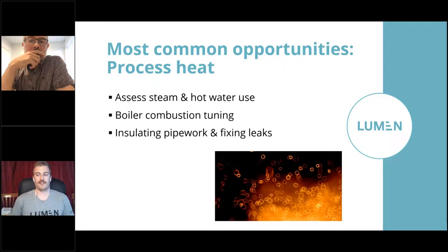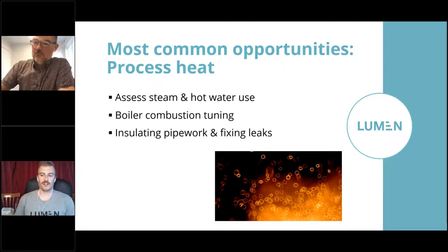The first thing we always recommend is to assess the steam and hot water use. Where's it going? How much is being used? Do we actually need that much? A good example is meat processing plants. I think we've got a few guys from meat processing plants here today. We've often found that knife sterilizer hot water flow rates are 3, 4, 5 times what they need to be. Hot water washdown hose flow rates are 2 to 3 times what they need to be to do the job effectively. And these are relatively easy things to measure. It can often reduce the heat load by 10, 20%.